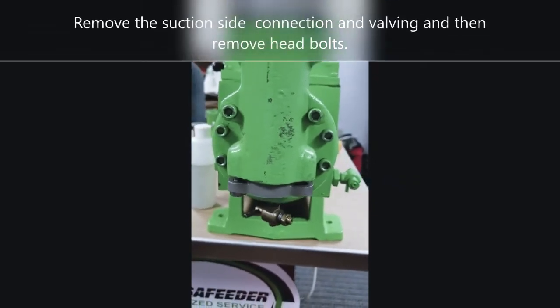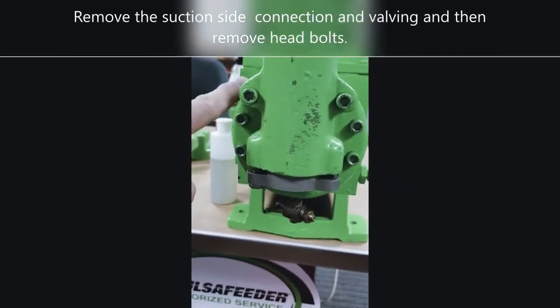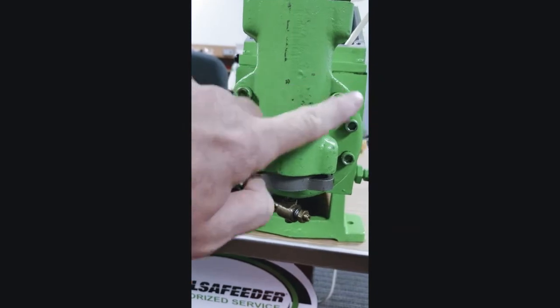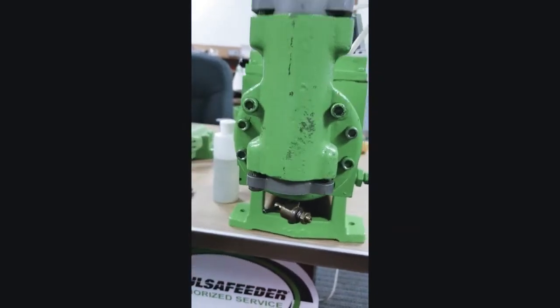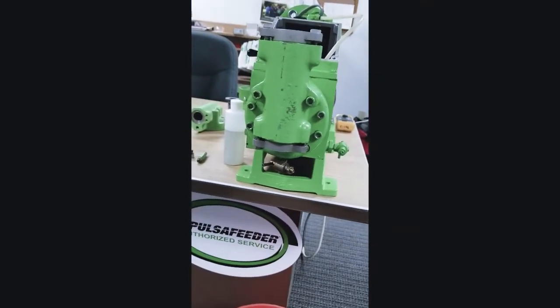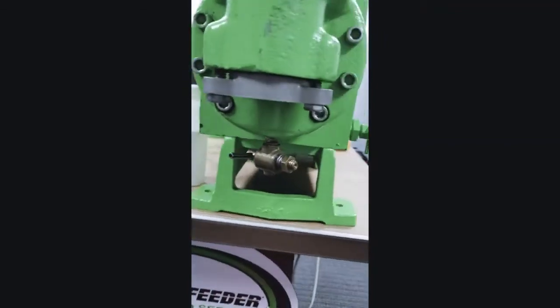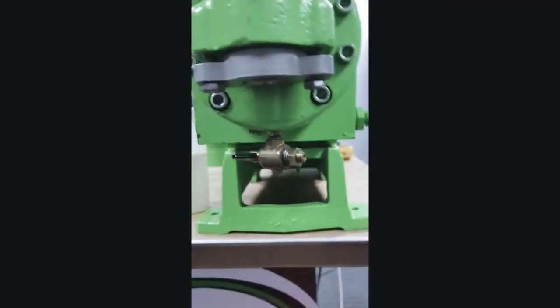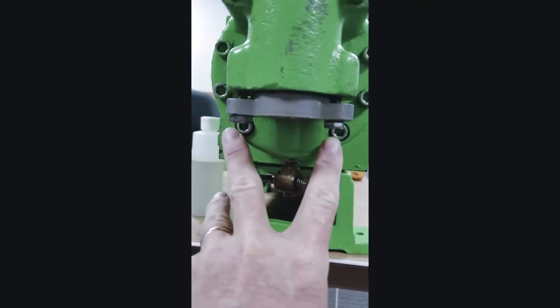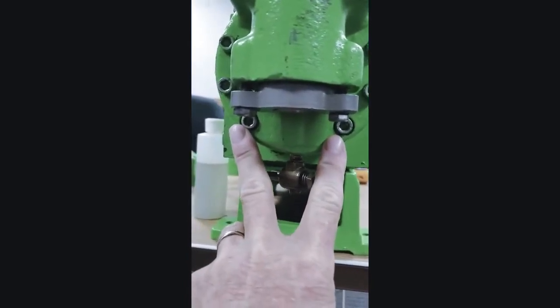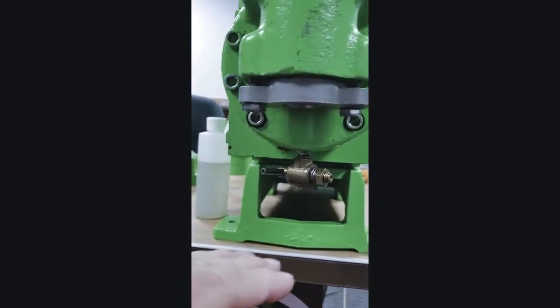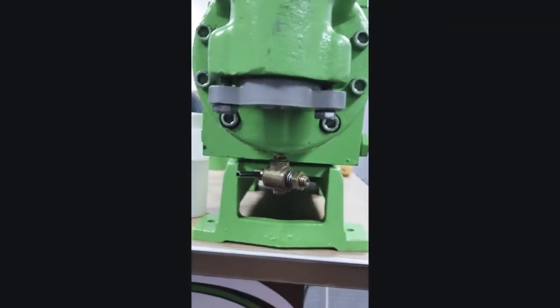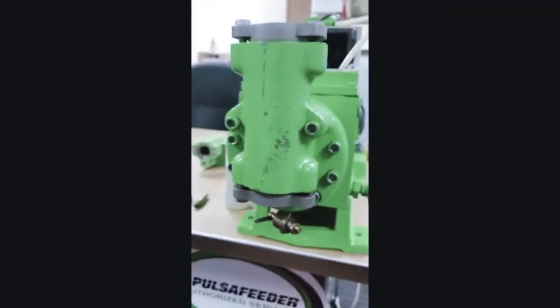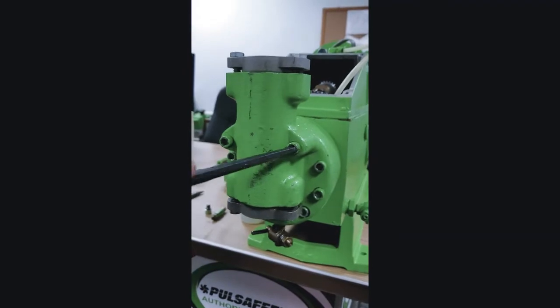With the intermediate head now drained, it's time to remove all of the head bolts so that we can remove our Hydratube head and change out that Hydratube. Please note that if your pump is still piped up to your system, these two lower bolts you will not be able to remove without removing your valving and connecting for the suction side. So I'm going to go ahead now and remove all of these bolts.